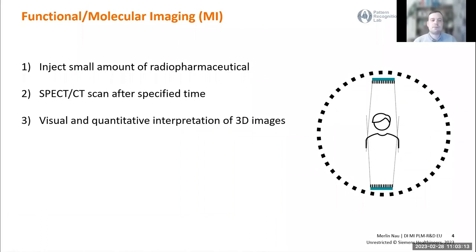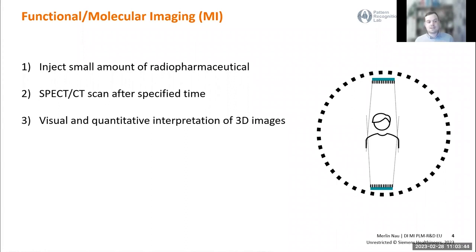For those not familiar with functional or molecular imaging, let me give a quick recap. In functional imaging, you start by injecting a small amount of a radiopharmaceutical to the patient. This is a radioactive isotope which emits gamma radiation and is bound to a tracer, which transports the isotope to a target tissue in the human body — maybe the bone, the brain, or the heart. After a specified time, you acquire a SPECT and a CT scan. The SPECT scanner has two detectors that rotate around the patient, and at each view these detectors take a so-called projection image.